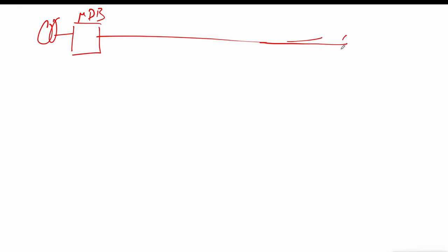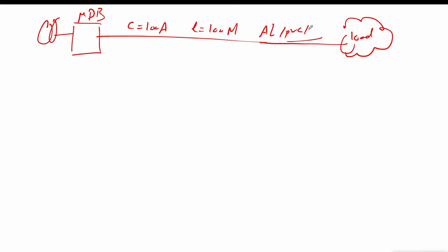We draw our example again: a power source connected to MDP and a load. We need a cable to handle 100 ampere current over a length of 100 meters. The cable is aluminum conductor with PVC inner and PVC outer insulation, installed at a depth of 0.8 meter, ground temperature 30°C, with three cables grouped in the same trench.